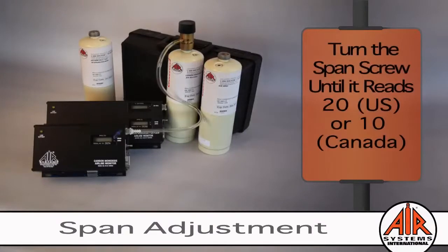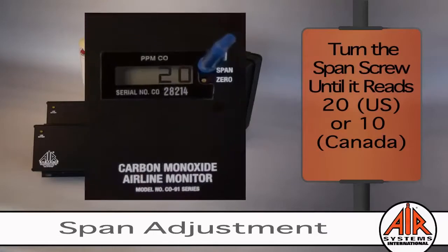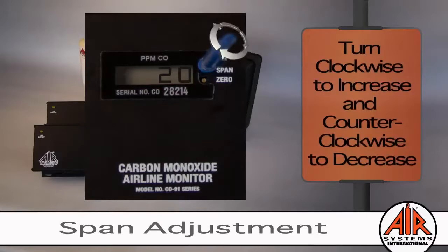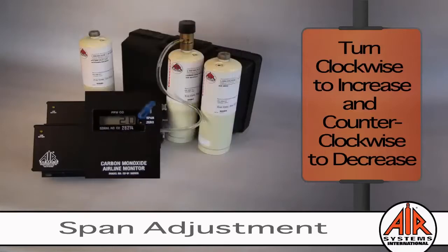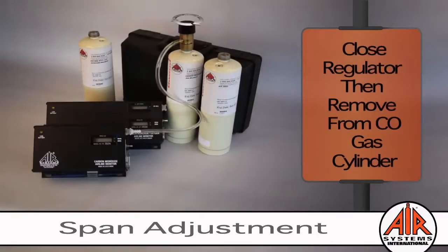Use the calibration tool to turn the span screw until it reads 20, or 10 if in Canada. This is achieved by turning clockwise to increase the value and counterclockwise to decrease the value. Close the regulator, then remove from the CO gas cylinder.